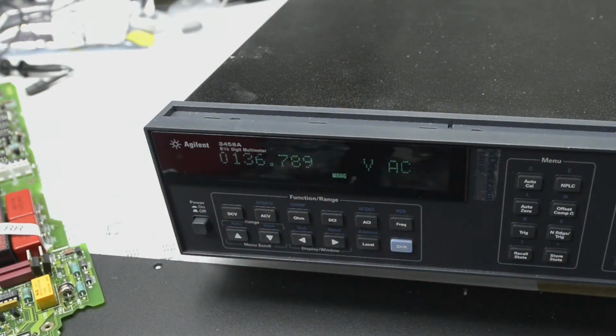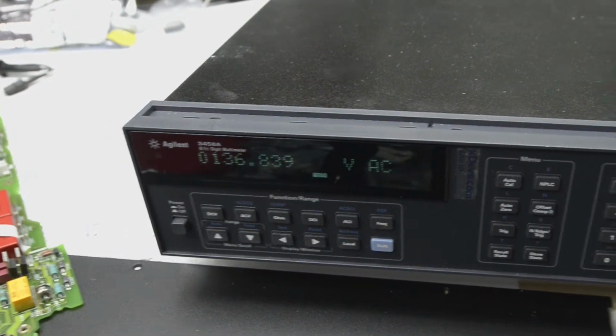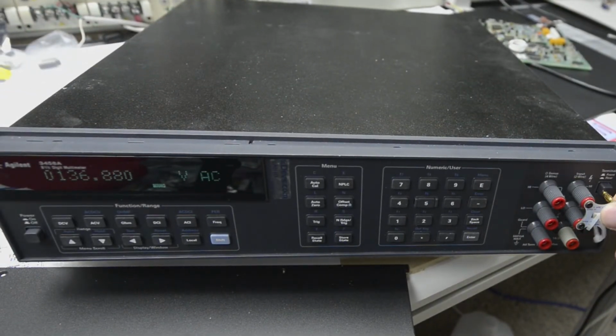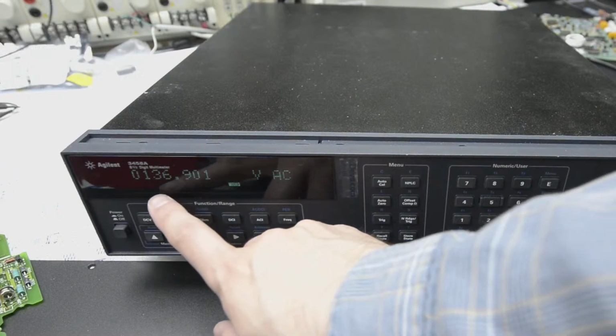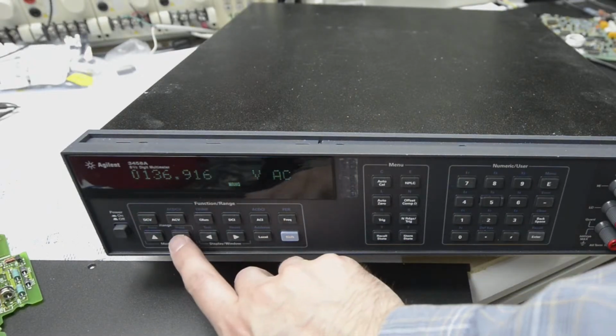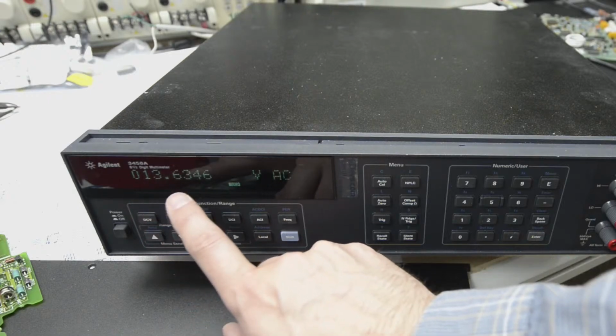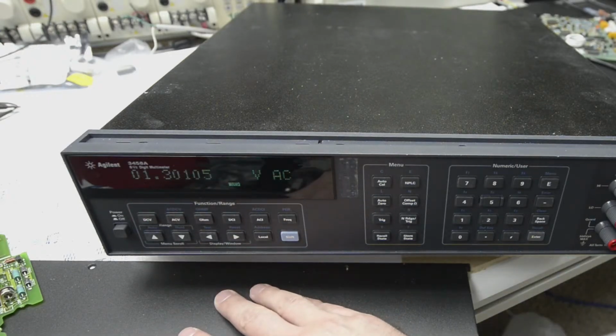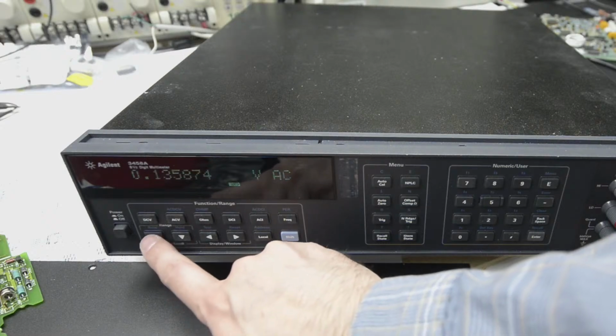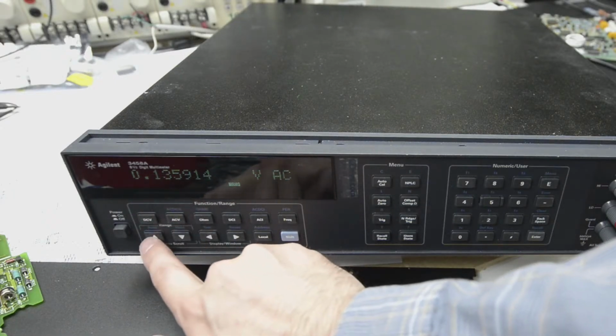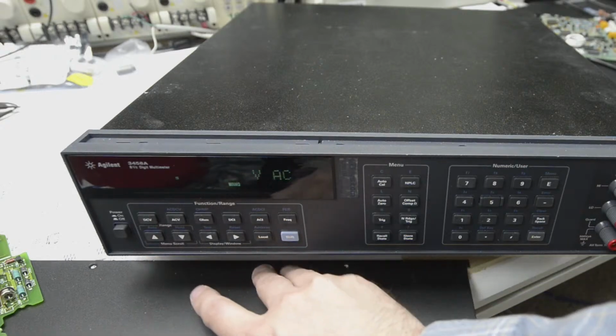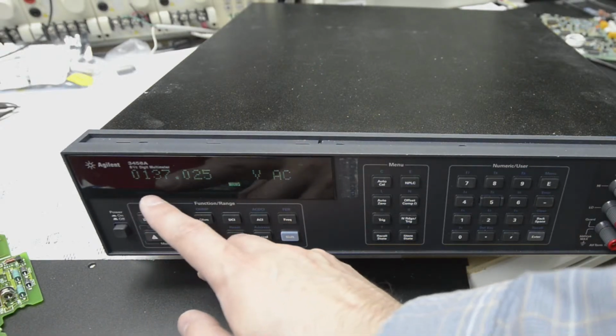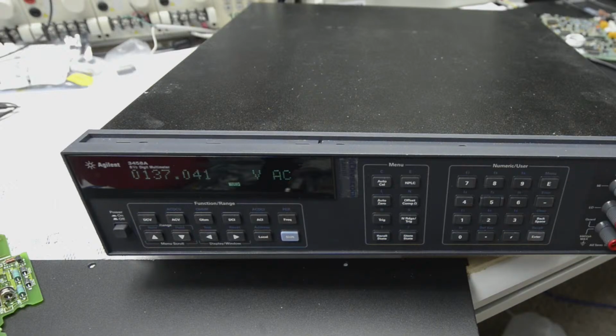so this is the issue that you would have with a broken A2. You can see the input is actually shorted right there. There is a shorting plug, but the meter reads 136, so it stays the same value. See, 136, just the dot moves. This is the typical problem when you have a broken A2. 135, 136 always stays, and it doesn't matter even if you use the kilovolt range. It shows you have 137 volts, but we have the input shorted to the copper link.